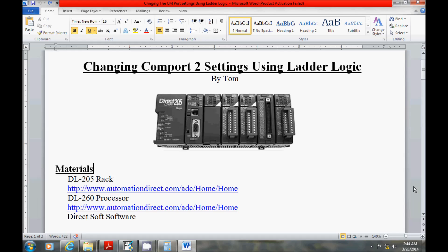I'm going to show you how to do it through the DirectSoft 5 software and also through Ladder Logic. There are a couple reasons why I like to do it through Ladder Logic. If you were ever to replace the processor, or even during initial startup, when you download your project you also have to go to the Comport settings, make changes, and then download them to your processor. I'm the type of guy who likes one-stop shopping — I like to do everything in one movement. With Ladder Logic I can make this happen automatically every time there is a power cycle of the PLC, or when you go from program to run mode.